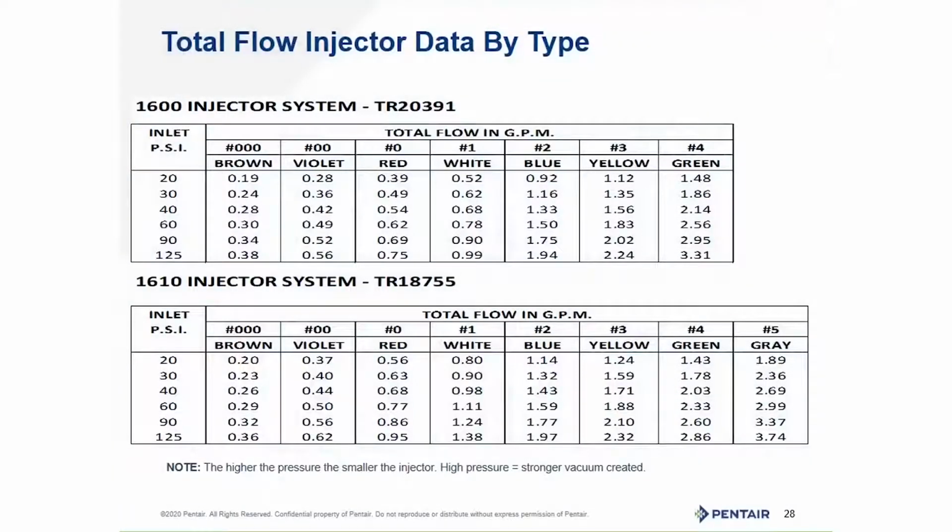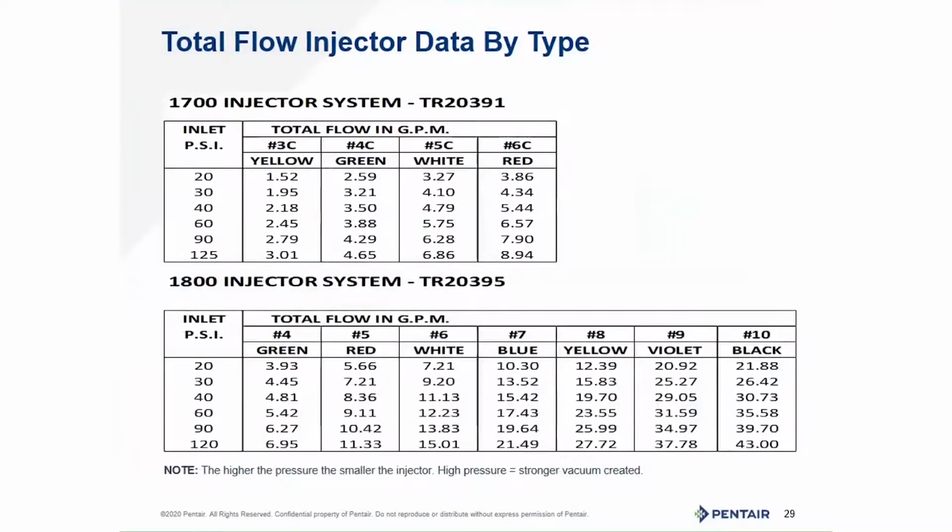So you have these charts in the back of every manual. Depending on the valve, you're going to have different charts to choose from. Now let's go ahead and take a look at that 10 cubic foot example where we were going to need, instead of 0.65 GPM flow rate, 6.5 GPM flow rate for 10 cubic feet of resin.